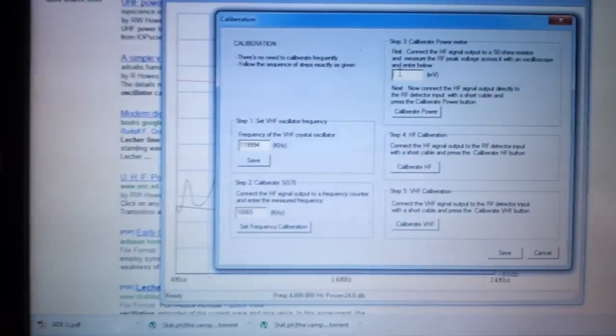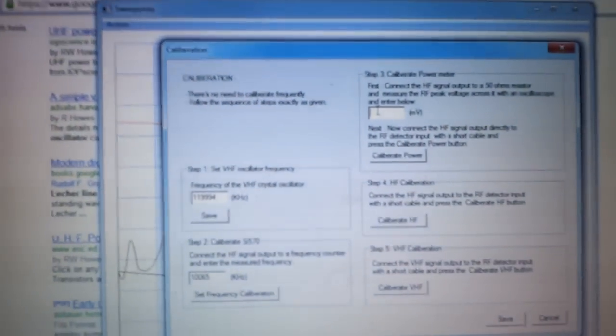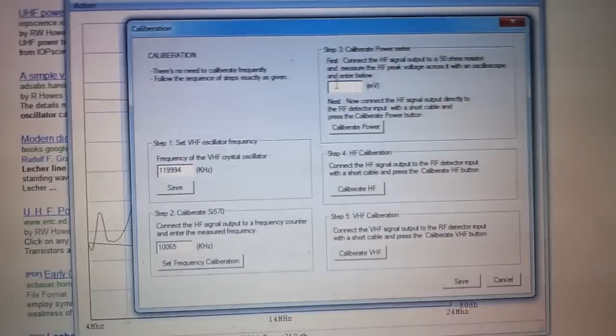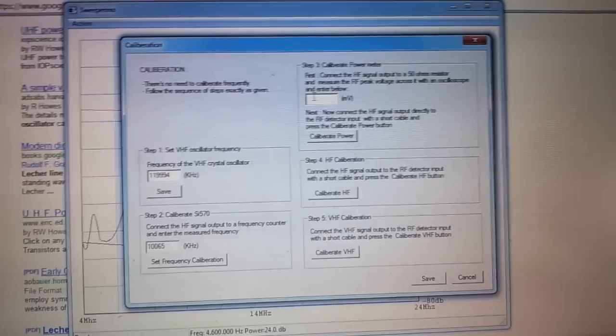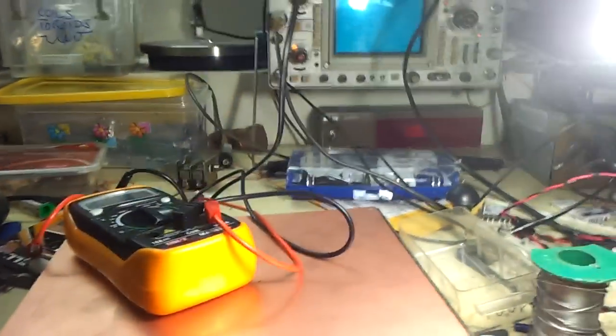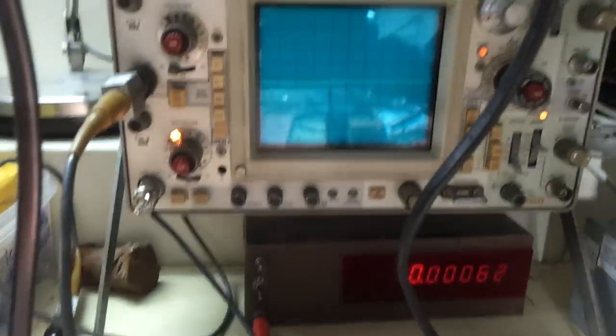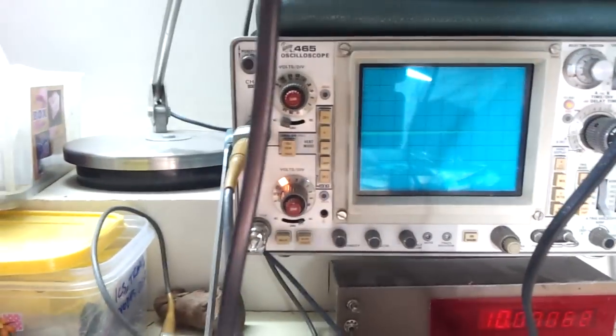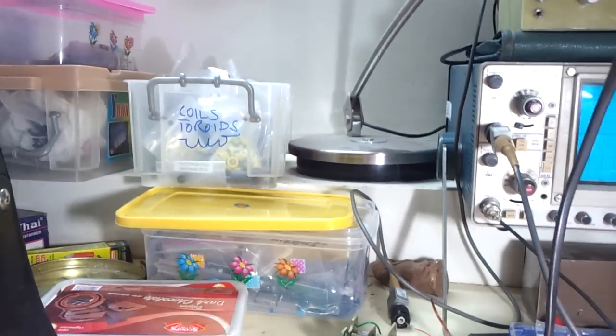The next thing that I do here is I calibrate the power meter. So I connect RF power out to the oscilloscope, which is here.